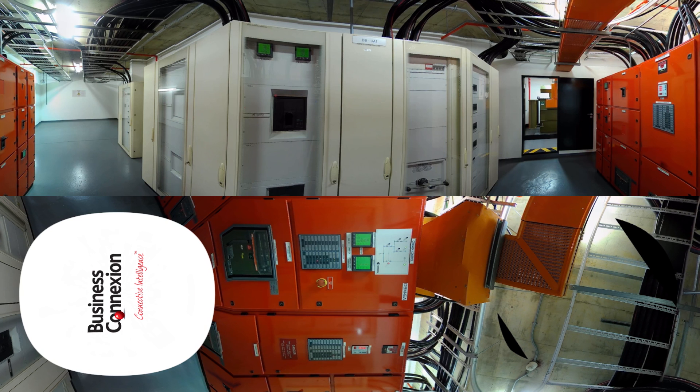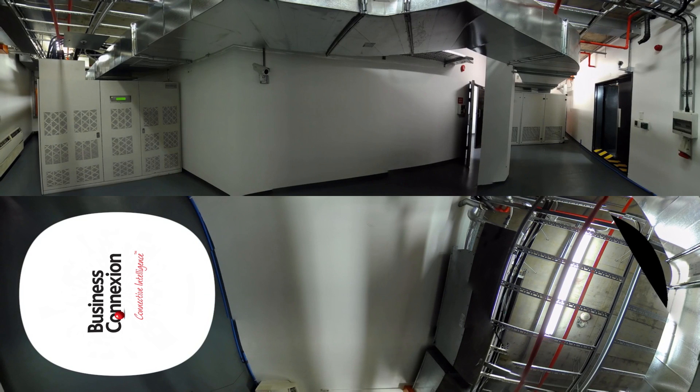Welcome to one of the power management systems in the data center. All the equipment in both NDC1 and NDC2 receive their power at all times from an uninterruptible power supply system, or UPS system. The UPS system can in turn be supplied by any electrical source, including power from the local electricity utility, power from the UPS's own backup batteries, or from the electricity generators installed in each data center. Using the UPS system as the primary power source, we ensure clean power to all electronic equipment, ensuring that even the most extreme power failure will not affect the computer room. If the power from the local power utility is lost, the UPS system will continue to deliver uninterrupted power to all equipment while the generators start working and reach level engine speeds.